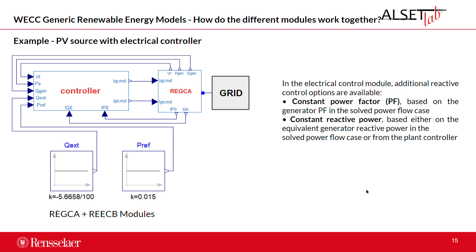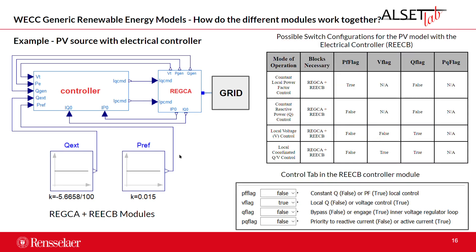This is an example of how to connect the electrical controller with the generator/converter model for the PV source. Through differences in the Boolean values of the switches, we can have different control schemes. For instance, for the PV controller, we have constant power factor control and constant reactive power control. These modes of operation have the minimum required blocks necessary; in order to have constant local power factor control, we need two modules with a specific logic configuration. An example of the control tab of the electrical controller is shown, where we have the Boolean values.